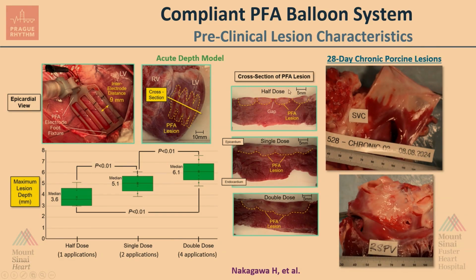So if we look here, this is some preclinical work that Hiroshi Nakagawa did using this sort of a very small type of electrode design. This is what the splines would look like. They put it on the ventricle and delivered lesions. You can see what the lesions look like. And you can see the lesion depths at half dose, single dose, and double dose, between 4 up to 6 millimeters in depth. And again, you see these are 28-day chronic lesions. You can see at half dose, there's some gaps in between. At single dose, it's relatively confluent, but some scalloping. And at double dose, it looks relatively contiguous with minimal scalloping.